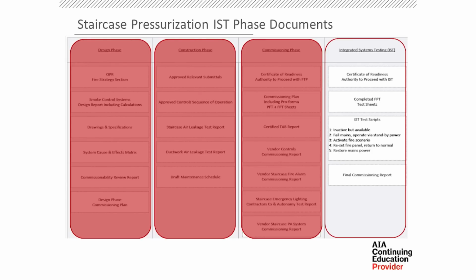IST - this is really what it's all about, the culmination of everything, and this is what matters. Integrated systems testing is about how one system interfaces with another. If you go back to the systems diagram, we've got staircase, ductwork, fire alarm, PA, elevators, lighting, and so on. These all have to work in conjunction with each other - they're designed to - and there are interfaces, some hardware, some software, between them. These have to be tested during integrated systems testing.